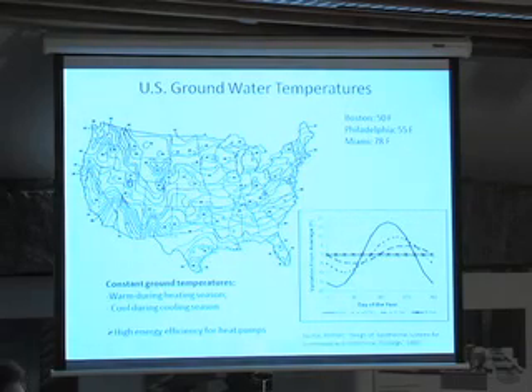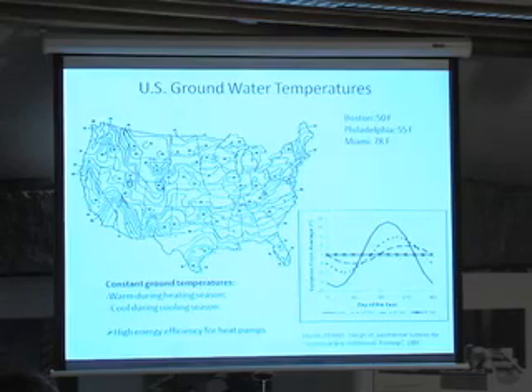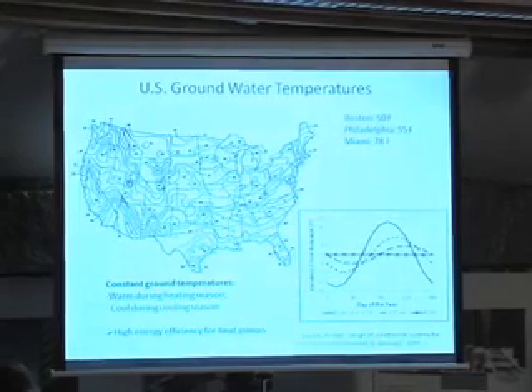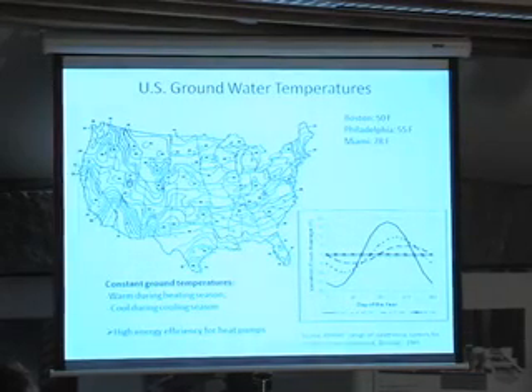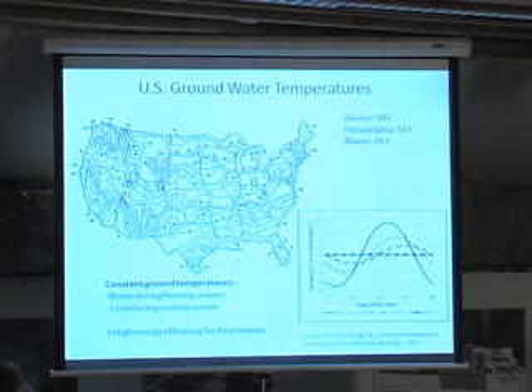Why do geothermal systems or these ground source systems go so deep? Well, because they're utilizing the boreholes as a heat exchanger. And the size of the heat exchanger is driven by the depth of the borehole. You need the heat transfer surface area to do a certain amount of heat transfer.